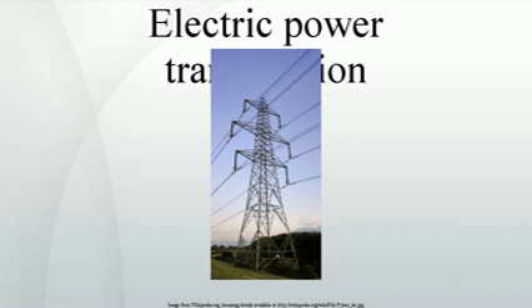The unvarying, or slowly varying over many hours, portion of the electric demand is known as the base load and is generally served by large facilities, which are more efficient due to economies of scale, with fixed costs for fuel and operation. Such facilities are nuclear, coal-fired or hydroelectric, while other energy sources such as concentrated solar thermal and geothermal power have the potential to provide base load power. Renewable energy sources such as solar photovoltaics, wind, wave, and tidal are, due to their intermittency, not considered as supplying base load, but will still add power to the grid. The remaining or peak power demand is supplied by peaking power plants, which are typically smaller, faster responding, and higher cost sources, such as combined cycle or combustion turbine plants fueled by natural gas.